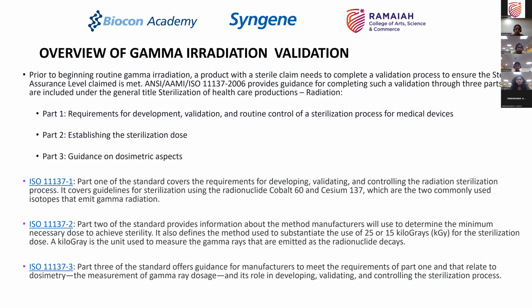It talks about both cobalt 60 and cesium 137. So, from the perspective of a guideline, it covers both the molecules. Cobalt 60 is what we will use more often. Part two is the information about the method manufacturers will use to determine the minimum necessary dose to achieve sterility. So we spoke about 25 kilograys as the standard used, right? But it could be 25, it could be 15, it could be even 40. So how do you decide this dose? This is what is covered in part two.